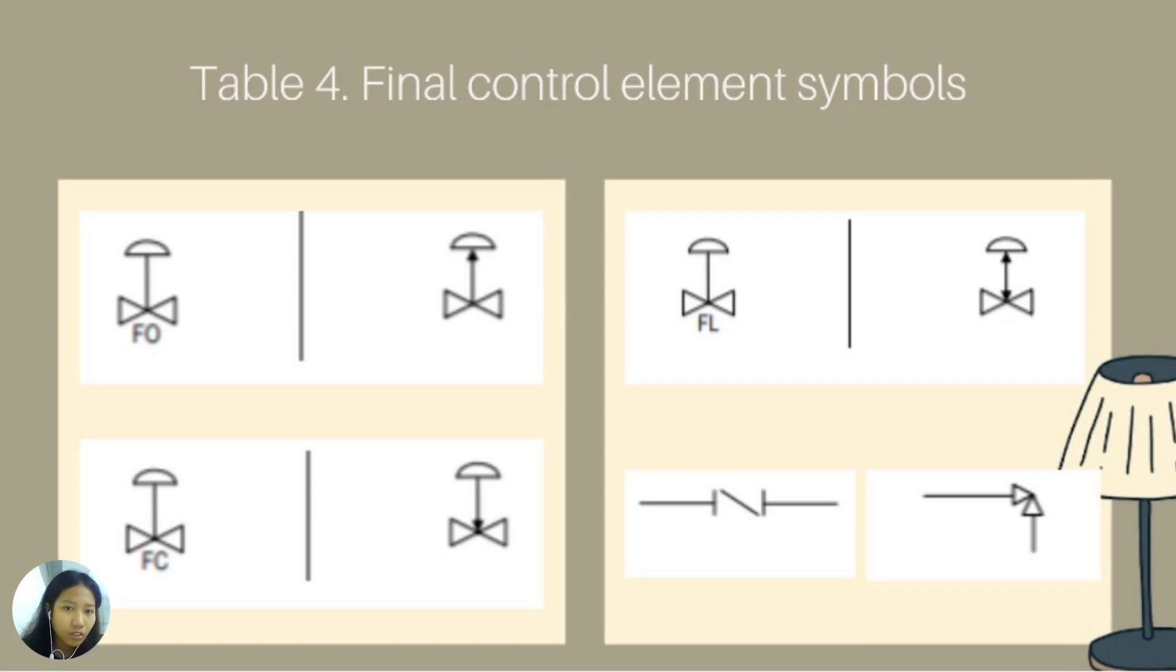For the next topic, which is the final control element symbols. The first picture is the symbol used for the fail open or the FO. When the power or air pressure is removed from the valve, the valve opens, and this is known as the fail open. For the second picture, it is the fail closed or the FC. When the signal is lost, the valve closes, which is known as the fail closed. If the valve was being used to reduce pressure, such as for suction control on air compressor, a fail closed valve will safeguard downstream equipment from high pressure in the case of a failure. And for the third picture, when the signal is lost, a control valve in the stem is left in its last position, and it is secured in that position. The force of the flowing stream pushes the valve plug to the open or closed position in the fail lock condition, or the FL.